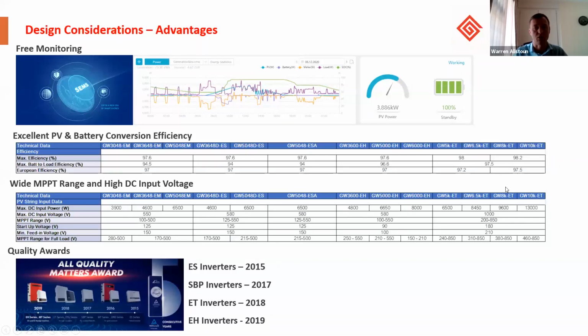Another advantage with GoodWe products is the high input range for the PV DC, so you can string long strings of panels, therefore reducing the need for string boxes and the extra costs for putting the system together. So with the EM series, we got a max voltage of 550, and for the ES and the ESA, 580. For the EH single phase, max input voltage of 580 again, and then our three-phase products offer a maximum voltage of 1000 volts.